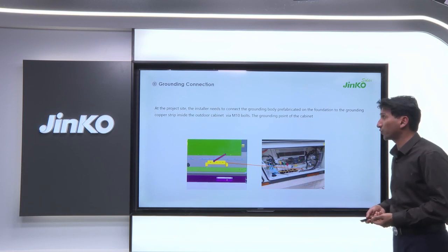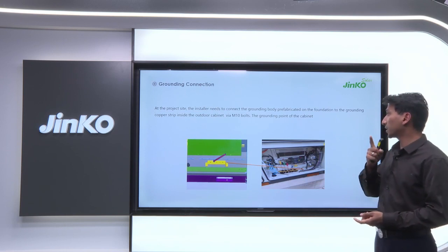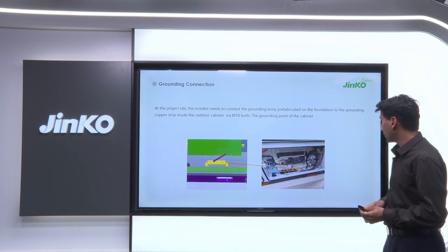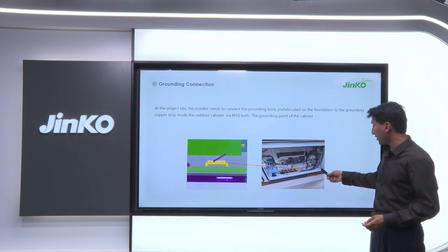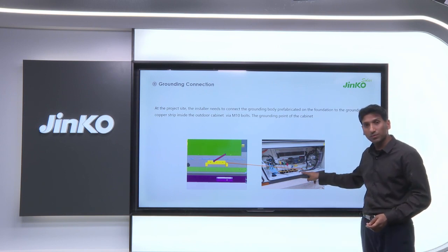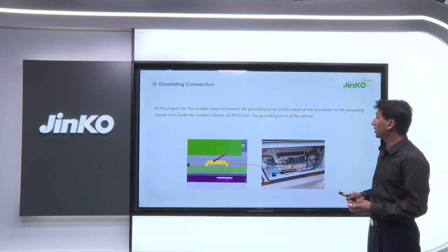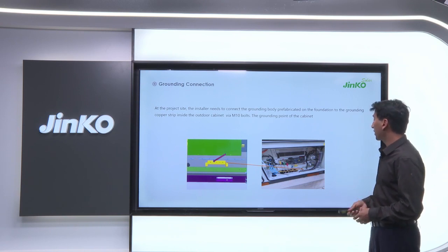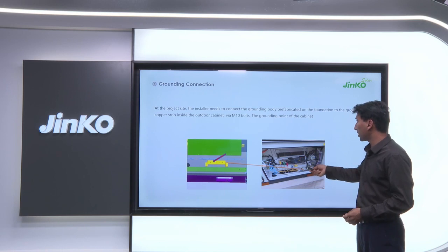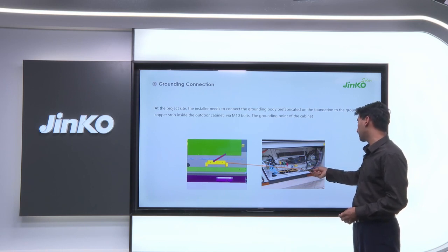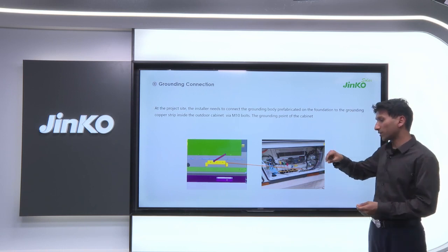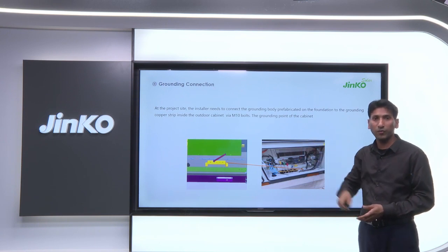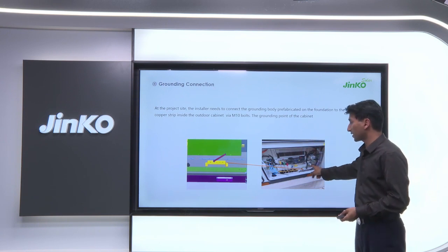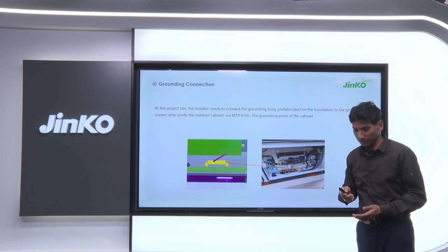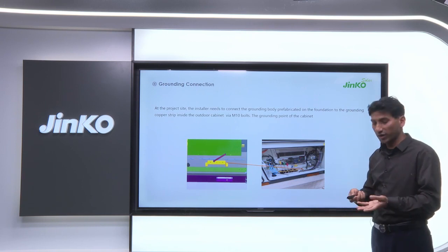Moving on, grounding. Okay, now we are moving to the connections. The first connection that we do is the grounding connection. As you can see in the cabinet, we have this copper strip. This strip is for the grounding connection, and from here you can use an M10 size bolt to connect all the grounding points that you have already made for the site with this, and then connect to your grounding points. This first part is done, the grounding connection is done.